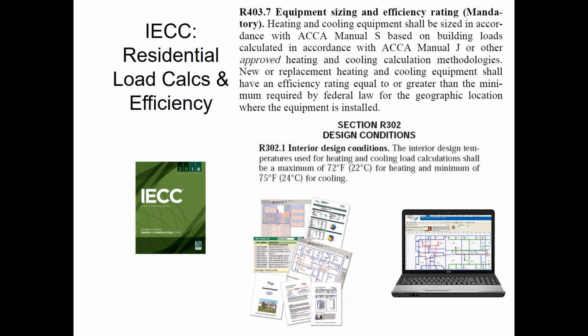It's also telling me here that I need to design for ACCA Manual S, which means how I size my equipment, and ACCA Manual J, which is how I do my load calc. Two things about that. ACCA Manual J is where I'm going to get my weather data from, so I'm going to show you that in a minute for the various states that you guys are in. And the other part of this I want you to pay attention to is it says ACCA Manual J or other approved heating and cooling calculation methodologies. We're going to come back to that statement later on, so just kind of keep that in mind here. ACCA Manual J is automatically approved. Other methods can be done if you can justify to your local authority that your method is good.